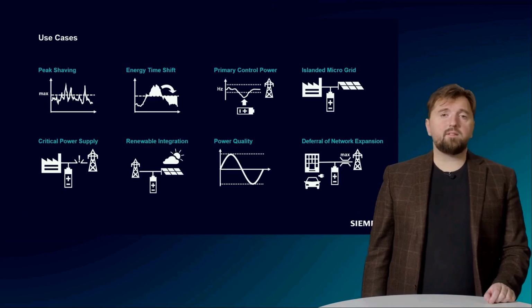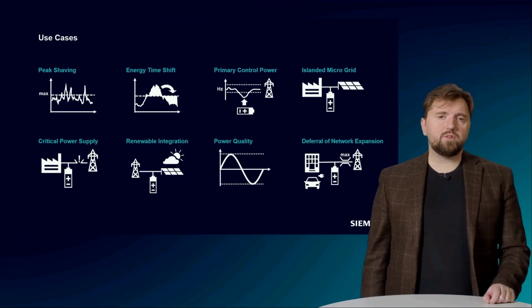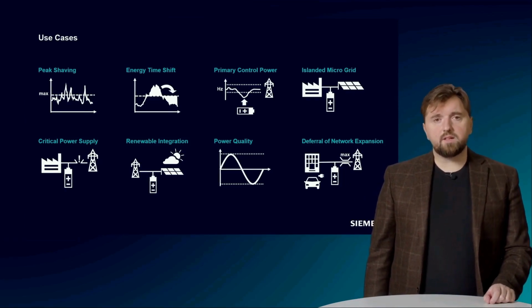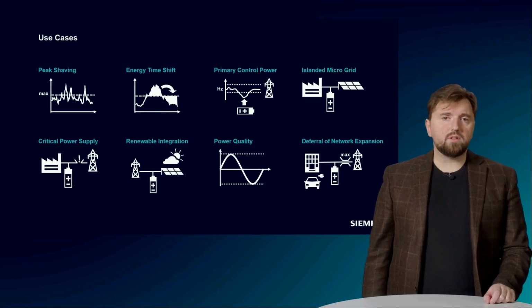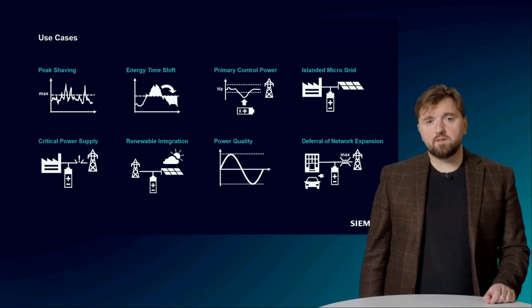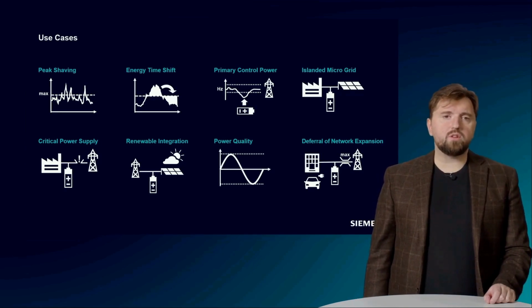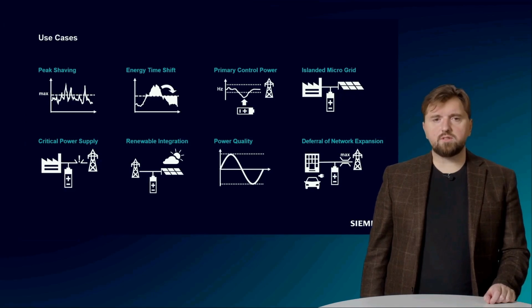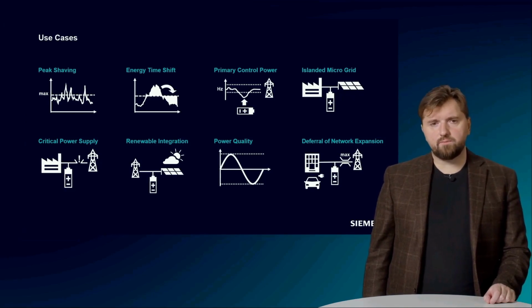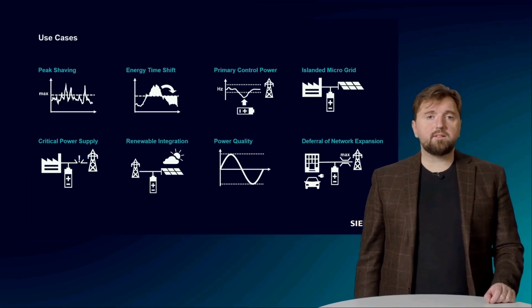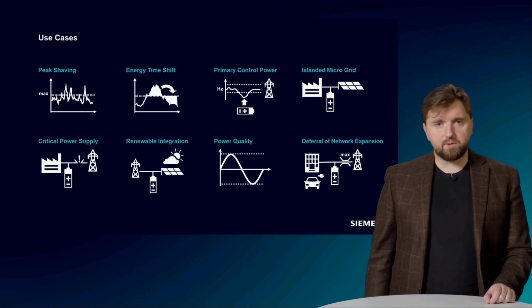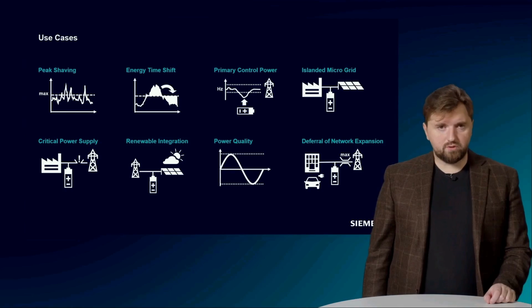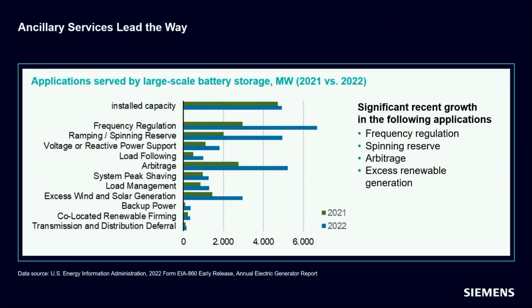We already said that BESS is a key enabler for increasing the share of renewables of the system. BESS evens out the ups and downs of wind and solar, increasing system flexibility. BESS can serve as an operating reserve. These are engaged to restore the generation and load balance in the event of a contingency, such as a sudden, unexpected loss of a generator. Lastly, utility-scale BESS can delay the need for expensive transmission grid upgrades, by giving us a smarter way to manage the grid. Recent development projects in the US have highlighted the growing significance of ancillary services in BESS usage.